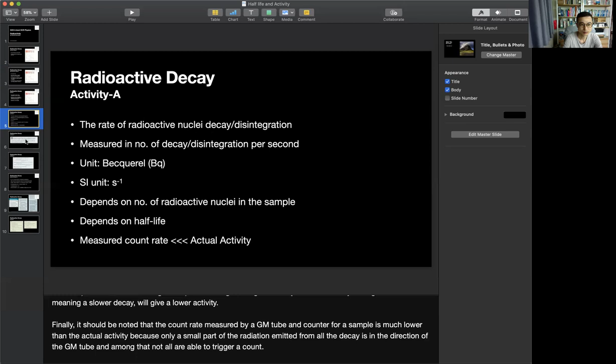Finally, it should be noted that the count rate measured by a GM tube and counter for a sample is much lower than the actual activity, because only a small part of the radiation emitted from the decay is in the direction of the GM tube, and not all of it is able to be counted.